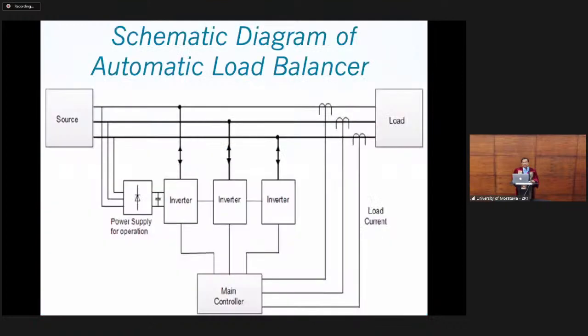So what we proposed is this: the source is the transformer, and we want to keep the three currents equal—that's our target. Since load currents can be high, medium, or low, rather than going to the source, we supply currents to an inverter system, the automatic load balancer, feeding the high load required phases, and drawing currents from the low current phases into our system, through a DC common bus, to invert them to AC and feed the necessary phases.